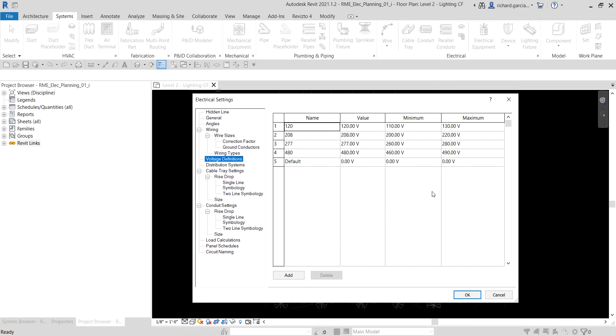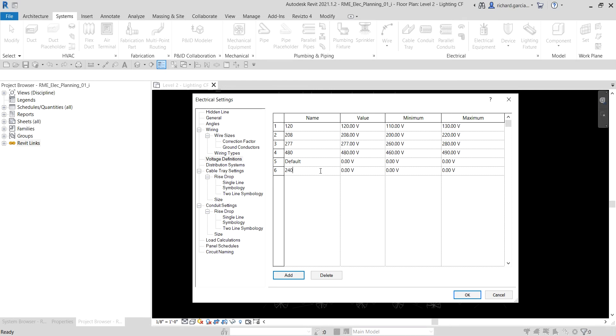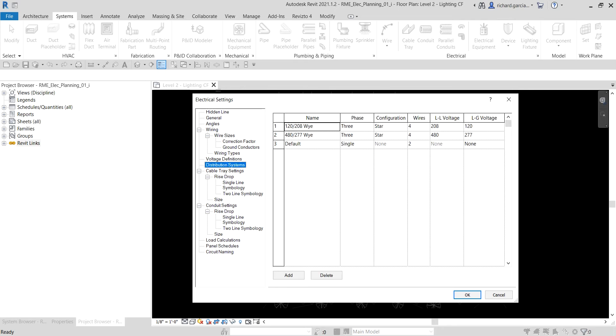Each voltage definition is specified as a range of voltages to allow for differing voltage ratings on devices from various manufacturers. For example, devices used on a 120-volt distribution system may carry ratings anywhere from 110 to 130 volts. Let's add a new voltage definition — I'll click Add, name it 240 Volts, set the value to 240, the minimum to 220, and the maximum to 250. That's our new voltage definition added.